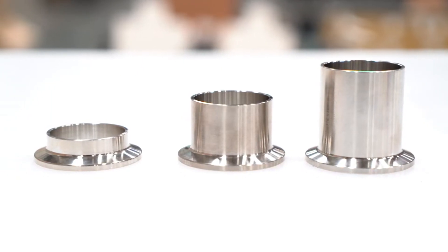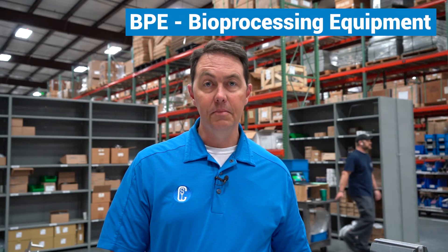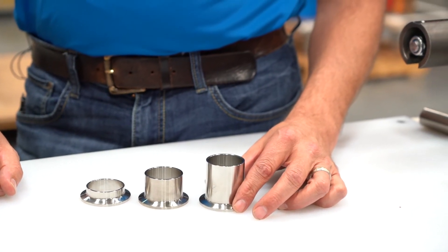Over time, as auto welding technology or computer-controlled welding became available, it became apparent that they needed some extra length or tangent to allow them to get better welds. That was where the longer tangents came from, and that dimension really started from ASME BPE, which is bioprocessing equipment, and they spent a lot of time figuring out what length was ideal for auto welding, at least based on the technology of the time.